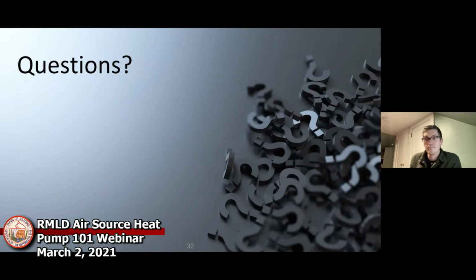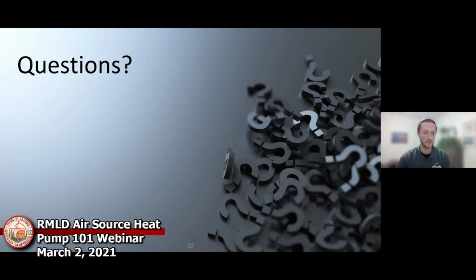So someone's wondering if they can install a heat pump in a garage. Maybe Christopher, you can answer that one best you can without seeing the garage. Well, I'll also pass it to Sean afterwards. So if that's like a workspace or workshop, I have seen people do that, and you'll just want to make sure, like Travis was mentioning, if that space is totally uninsulated and you expect a heat pump to try and keep it warm, and you're going to be opening and closing the garage doors a whole bunch, you might find that the heat pump has a hard time maintaining the temperature you're looking for in that space.